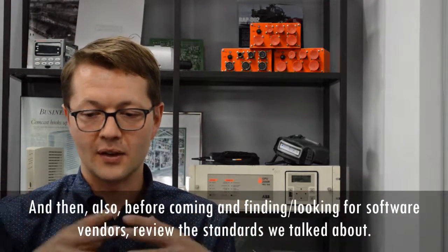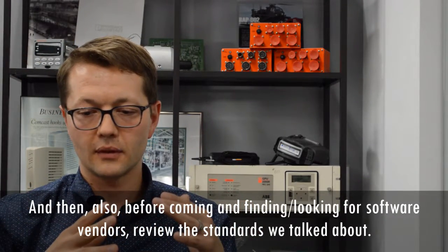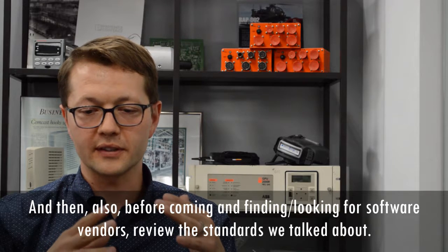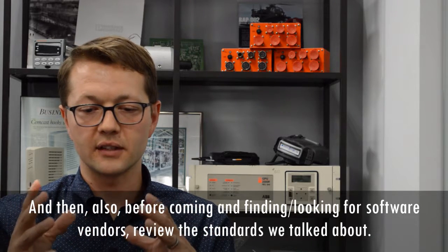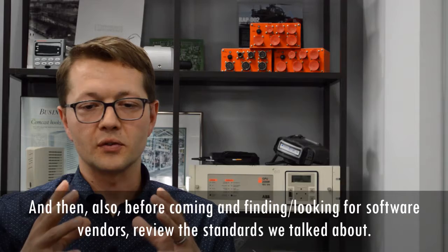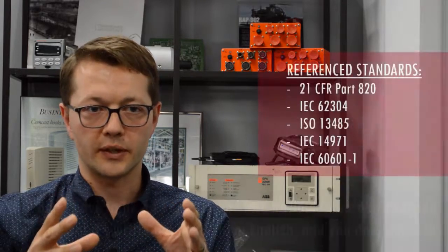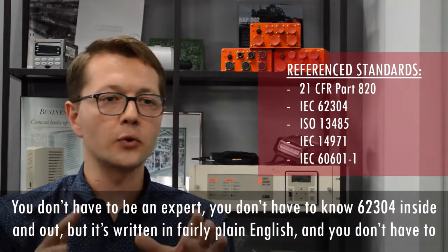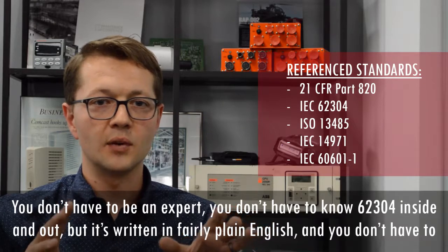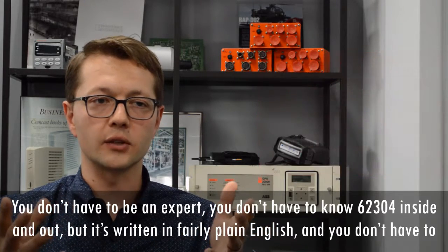And then also, before coming and looking for software vendors, review those standards that we talked about. You don't have to be an expert. You don't have to know 62304 inside and out, but it's written in fairly plain English.